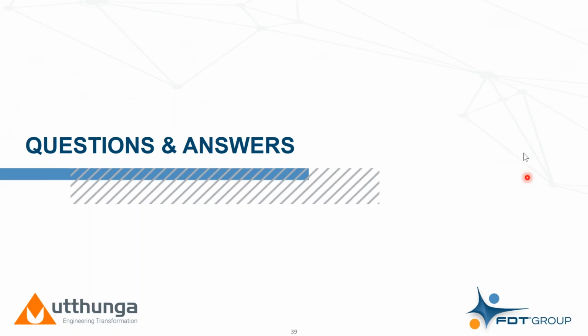And this one sounds like somebody that is from the industry. What is the refresh time of the FDT OPC UA server in the example of the HART device? Do you continuously poll data? If yes, what's the influence on the network load? Well, using HART as an example is kind of an interesting one, because HART, from a protocol perspective, classic HART, is really the slowest of all device communication protocols that's in the marketplace. So you could easily choke a HART device simply by constantly requesting data from it.